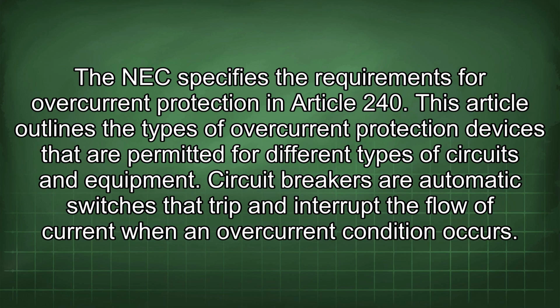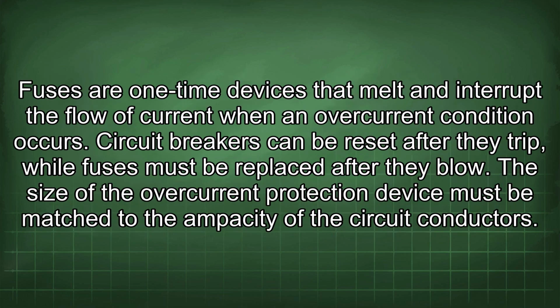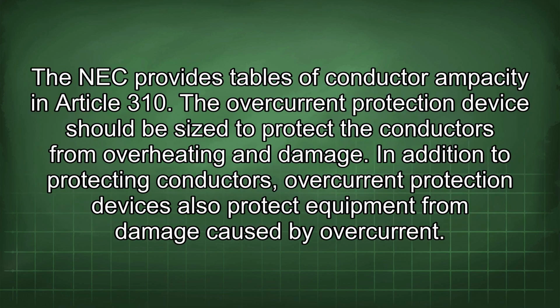Circuit breakers are automatic switches that trip and interrupt the flow of current when an overcurrent condition occurs. Fuses are one-time devices that melt and interrupt the flow of current when an overcurrent condition occurs. Circuit breakers can be reset after they trip, while fuses must be replaced after they blow. The size of the overcurrent protection device must be matched to the ampacity of the circuit conductors. The NEC provides tables of conductor ampacity in Article 310. The overcurrent protection device should be sized to protect the conductors from overheating and damage.